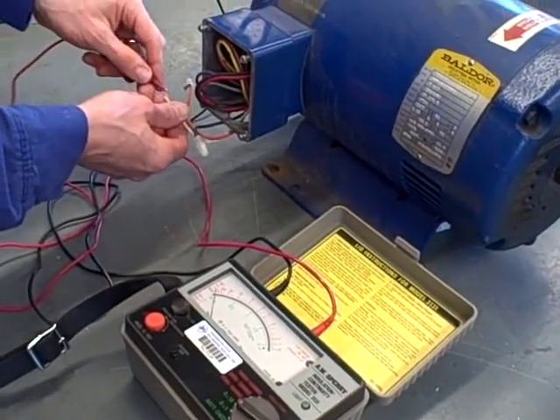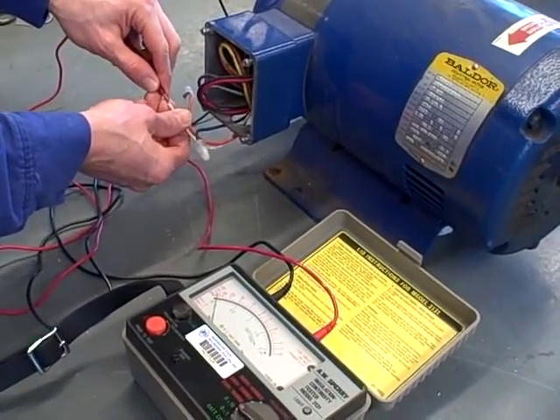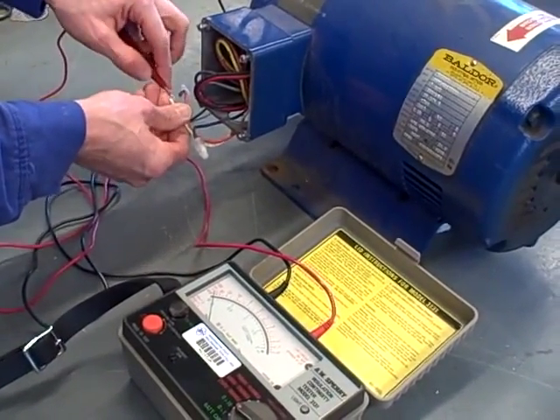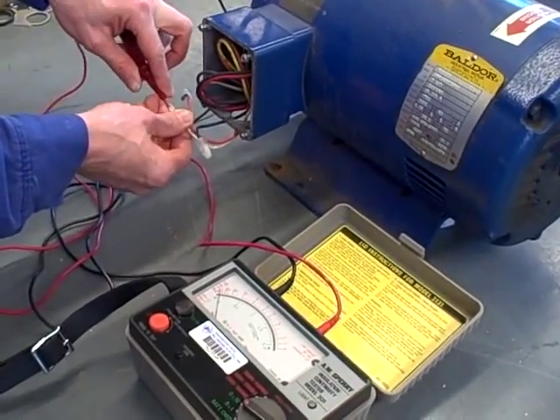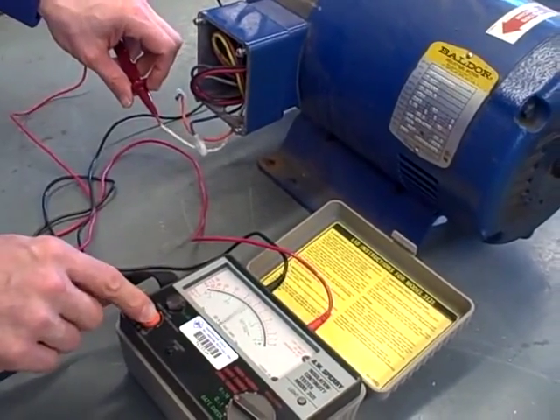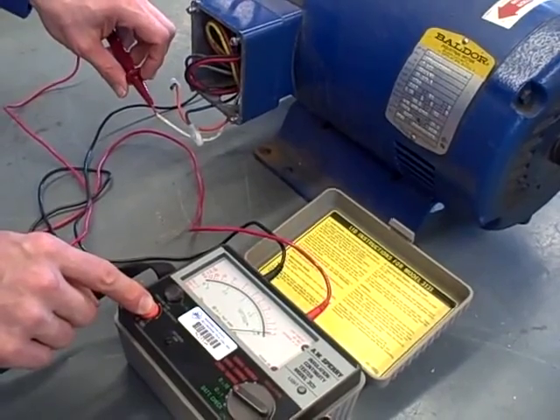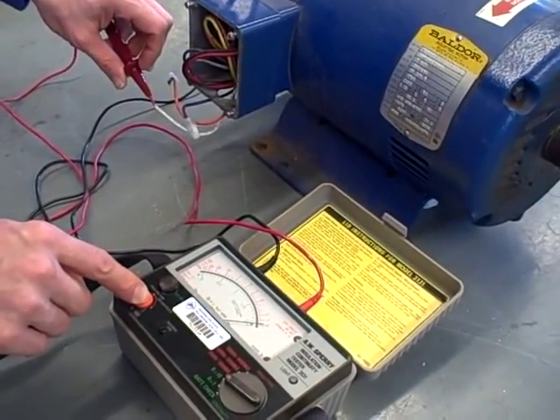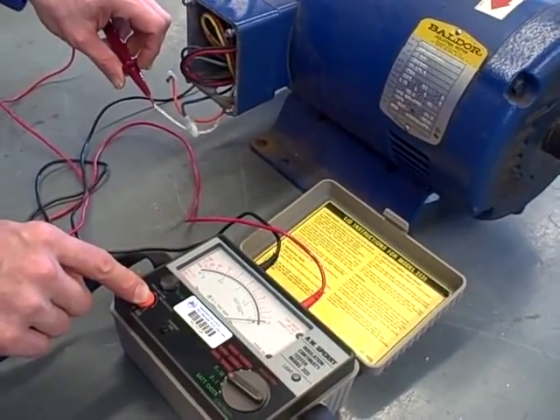Keeping that in mind, I'm going to make my connection here again with the phase winding, as such, and push the test button. Notice it swings to the right. Remember, in this mode, that means open. That would indicate a good winding.